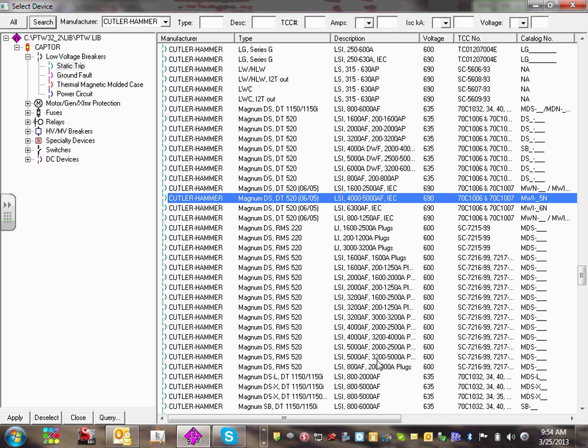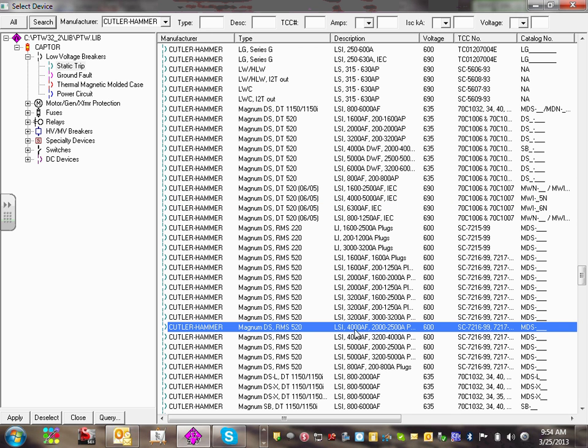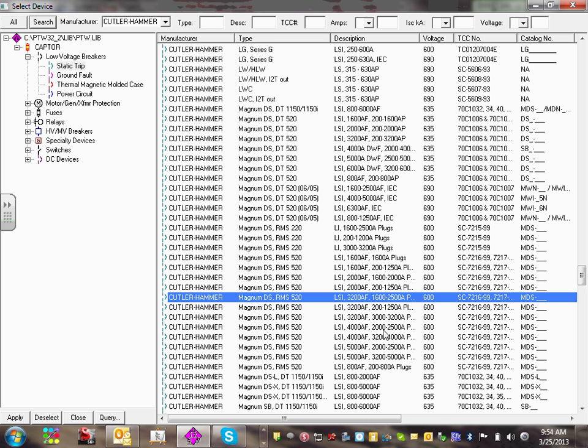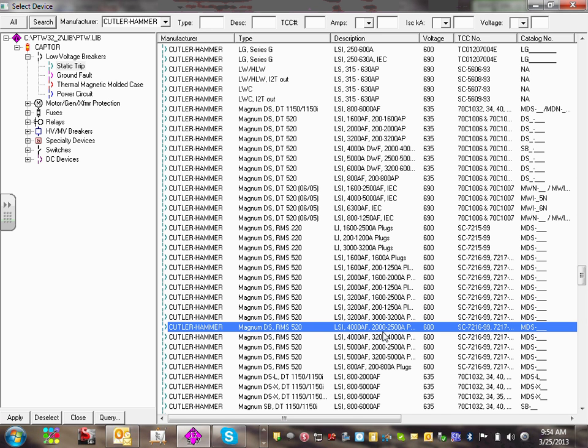552. Really, any of these long time options, I need one that says long time, short time, instantaneous, guys, and one that gives me a lot of amps because I have a big range for my circuit breakers. So a 4,000 amp frame, a 2,000 to 2,500 amp plug wouldn't get me there, right? Let's use this one for the main. Long time, short time, because the main is 4,000 — that would work. Everybody okay with this one, guys? Long time, shall we? Okay.